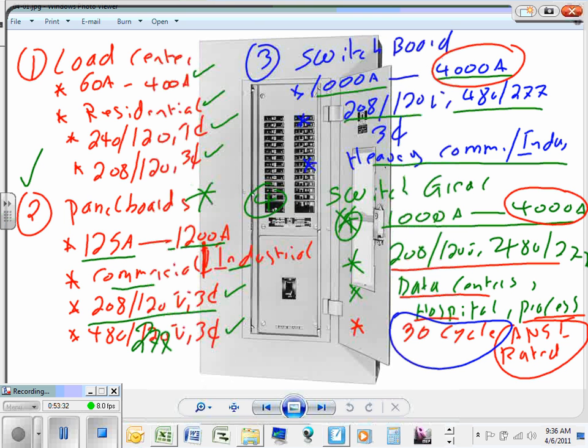Now, who cares about this? That allows you a lot of coordination, guys. It allows you to set the main at 30 cycles, and downstream you will set them at 20 cycles, 5 cycles, 3 cycles. So if you have a short circuit on a 600 amp panel, it would never take out the 4,000 amp switchgear, ever. Because you allow the short circuit to sit for 30 cycles on the main, while in the panels underneath it, it has to trip within 3 cycles. So that allows a lot of good coordination, guys.